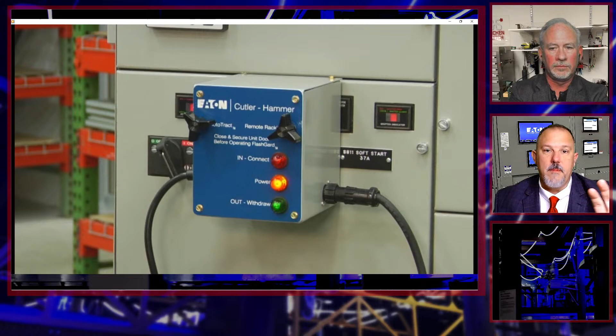You guys have products that'll do the same type of deal, just like you showed with magnets. This will start to pull that off the bus, and you'll watch the indicator go from red to green. There's a test condition, and I think if you look at the side of the bucket, it'll tell you when you pull it out to a certain point, when you're off the bus but still energized with, say, 120 volts, and you can test things. Then you pull it out further and you're completely disengaged.